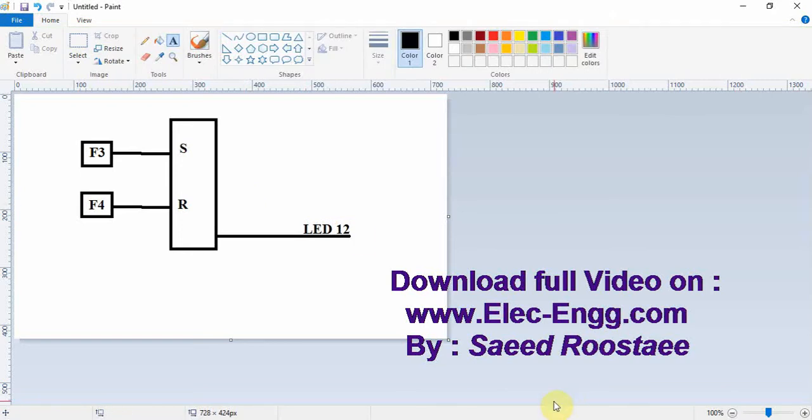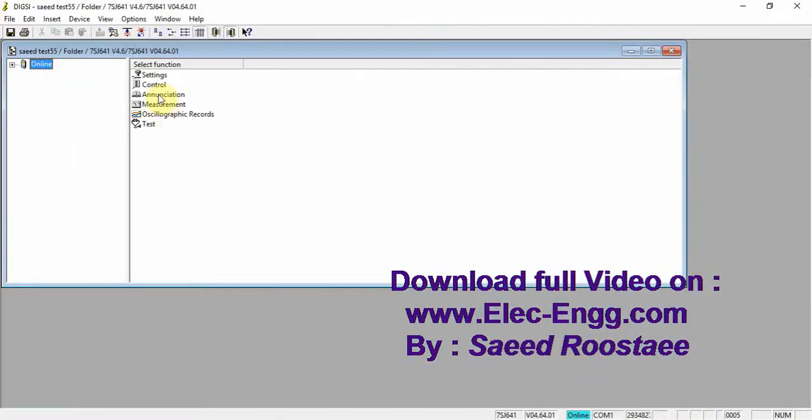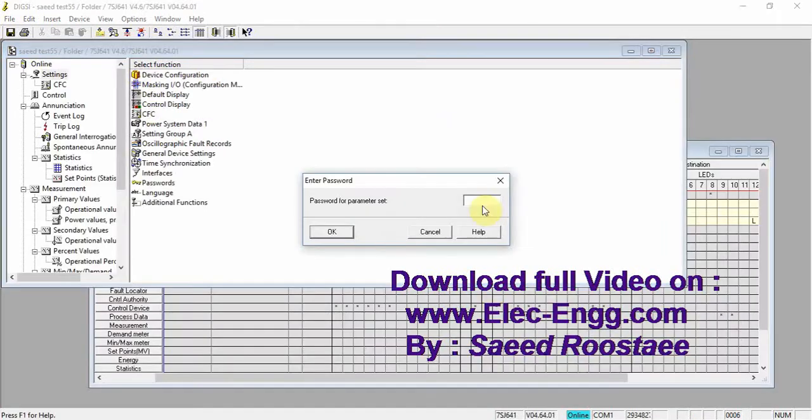Let's implement this simple function into the DIGSI software and download it to the relay and test it. So let's start. First of all, we have to go to password for parameter set.